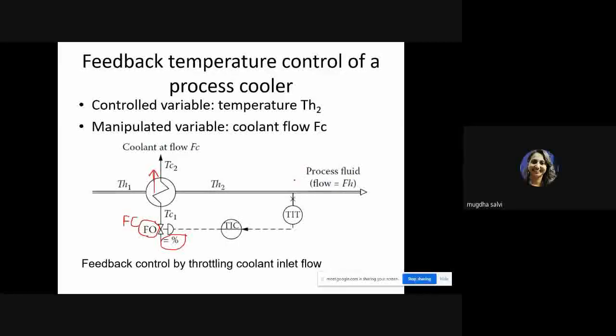So to avoid such a situation and any overheating or excessive damage to the heat exchanger, whenever there is a cooling action, the valve will always be fail to open. And whenever there is any heating action or some hot fluid, for example hot liquid or steam, this valve would always be fail to close.